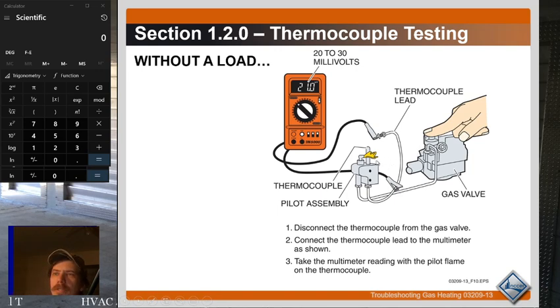So you're actually using the fire to create a voltage in two dissimilar metals, and that's what allows the gas valve to stay open. Alright, so if you're trying to troubleshoot one, this is a good picture here of what you do. You need to hold the pilot knob down, right, to keep the flame on. Then you have to hook up your meter from the tip, right, the tip of the thermocouple that screws into the gas valve to the copper part of the thermocouple going down. So this is hot basically, and this is ground.